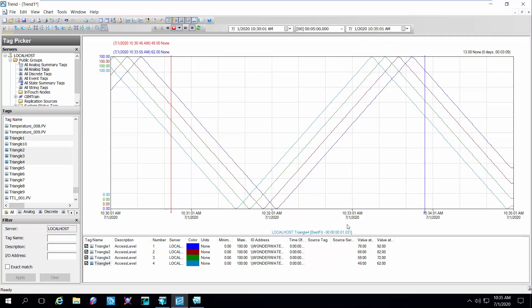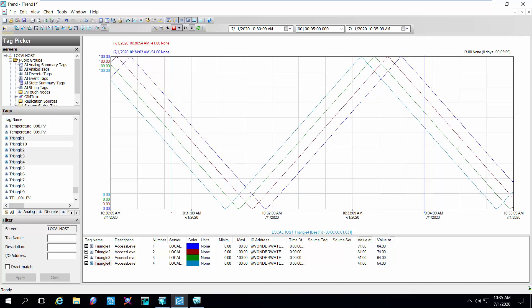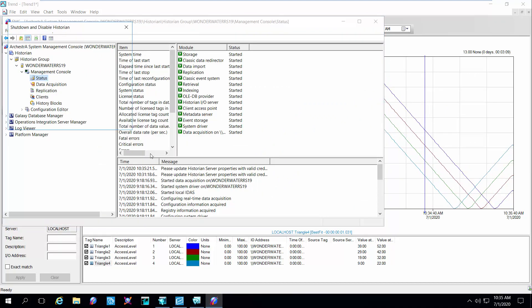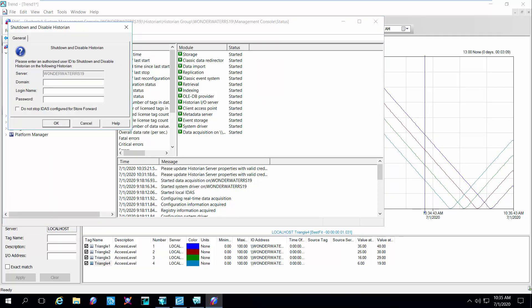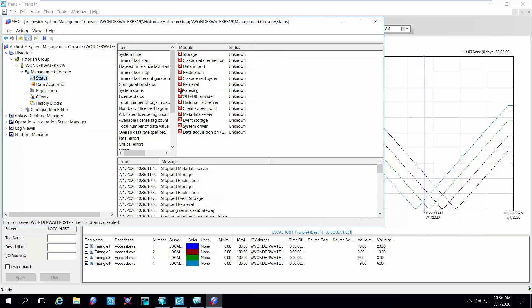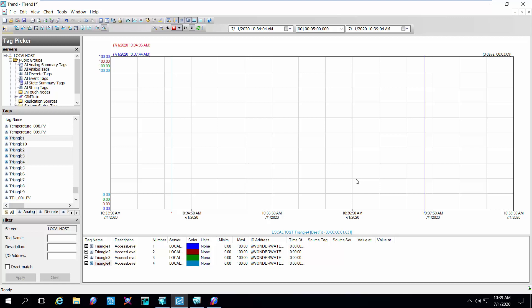So now you can see the data coming from that InTouch application in our trend. Let's demonstrate the store and forward capability — we're going to shut down the historian. If I right-click on the status, all tasks, I'm going to shut down and disable this historian. You can see we're starting to stop some of the processes running to keep the historian running. So the historian is stopped, and if I look at my trend application, you're going to see that the data indeed is flatlined — I'm not getting any new information. The trend is frozen and the historian is down. But the good news is that my InTouch application is buffering all that data, so when I bring the historian back online, we should see the data being backfilled. My trend is blank now because there's no historian running to retrieve information.